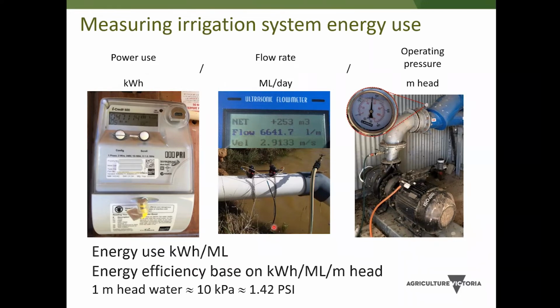Now, when we want to know the efficiency of that irrigation system, we also need to know the pressure that it's operating at. So we need a pressure gauge as close to the pump as we can get. And we also need to get an estimate of the suction side of the system. So how much suction pressure is required, but that's a much smaller component of the total pressure. And we can usually estimate that. So that gives us what we need to calculate energy efficiency, which is kilowatt hours of energy per megalitre per metre of head. Metre head is just another unit of measuring pressure. 1 metre head is equivalent to about 10 kilopascals or 1.4 PSI. It's a bit tricky in irrigation. A whole range of units are used, but in our energy tool, we've developed it so that you can just put in whatever units are on your equipment or on your gauges, and it'll do the conversions to metres head for you.